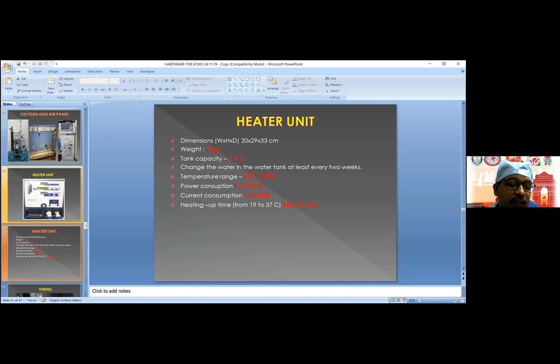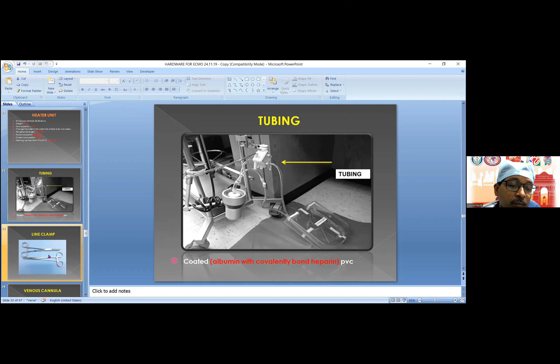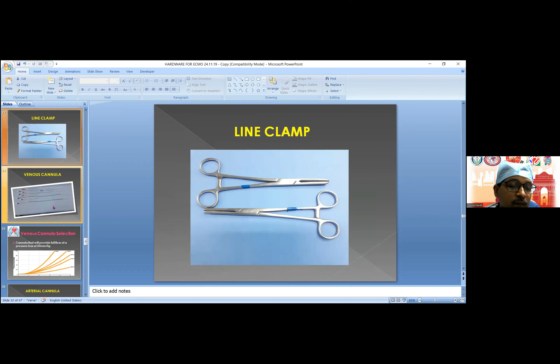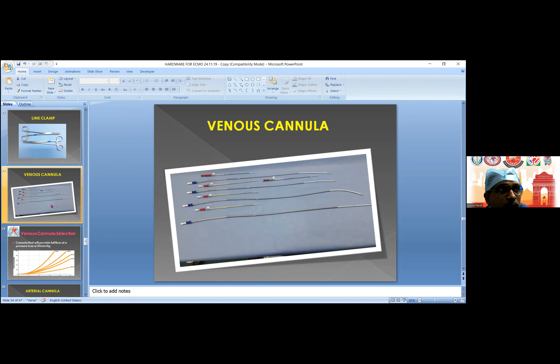This is the tubing. Nowadays, PVC tubing has improved. It is albumin and heparin coated, so that the activation is reduced, which lets us reduce the use of heparin, and the patient does well. For different reasons, such as a circuit change or any initiation of the circuit, we require a clamp and cannula. It should definitely be chosen according to the patient's body weight, vascular lumen, and how much blood supply is needed. Based on all these criteria, we calculate and finally decide which cannula to use for the patient.